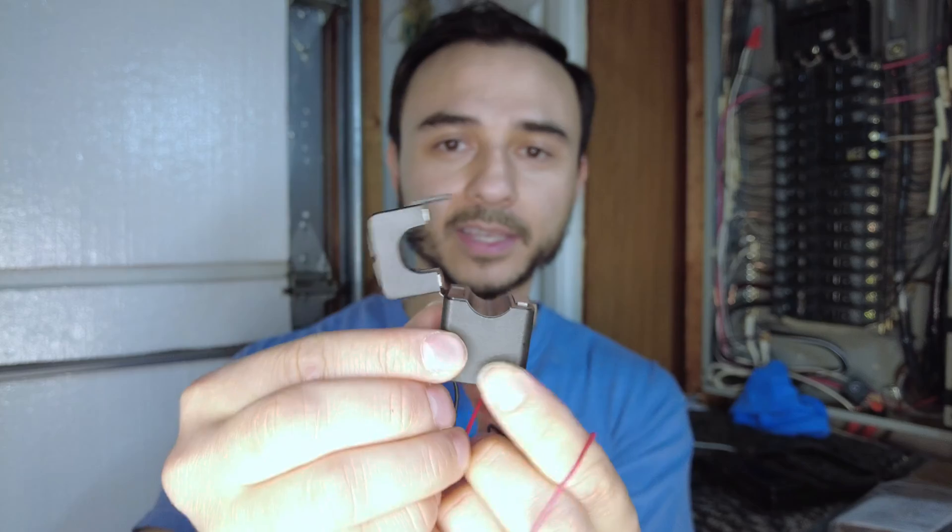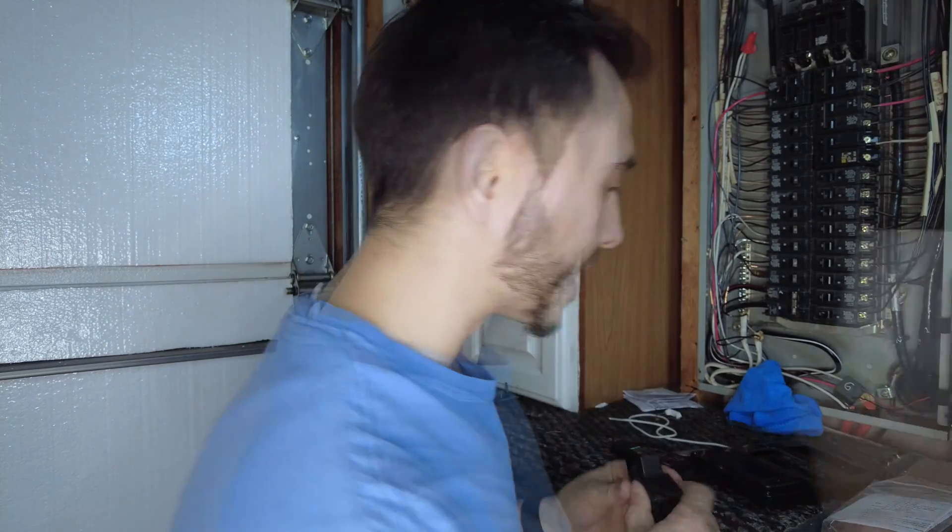As you can see it has a little clip on the side — you lift that up and it opens so you can wrap it around a wire. If you didn't get one of these you're going to have to either remove the wire, slide on the current transformer, or cut the wire. That's a lot more work. Get one of these — they work really well. Now I'm going to show you how to wire this up.